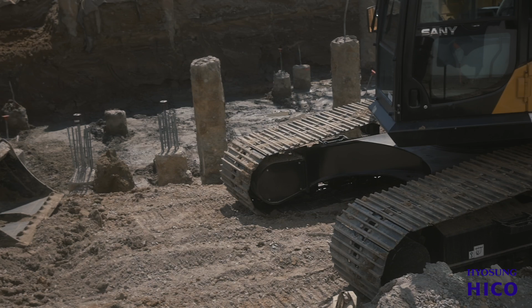We currently have 1 vapor phase dryer that we use for drying the windings and for drying the active parts after assembly. With the new construction project and the vapor phases being installed, we're going to use those 2 vapor phases to dry the active part before we tank it into the transformer tank. The new construction will house 2 vapor phases, with capacity for a 3rd in the future if we choose to bring another one in.